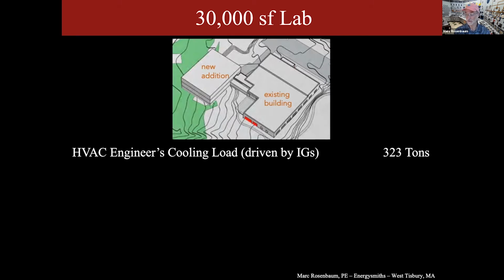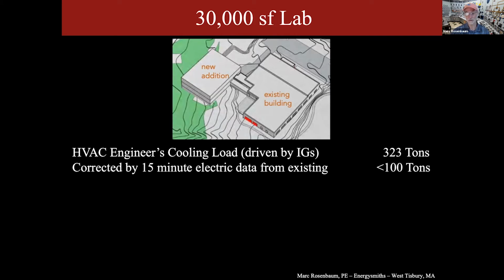I had them get 15-minute electrical data for that building, because this engineer's load is driven by the internal gains. I said, well, we've got electrical data for the existing building, let's look at it and see what we think those gains really are. So we looked at a year or 2 years' worth of 15-minute data to look for the maximum, and we found it. Then we subtracted the clearly large loads that didn't contribute to a cooling load, like some of the fans, the exhaust fans and stuff.